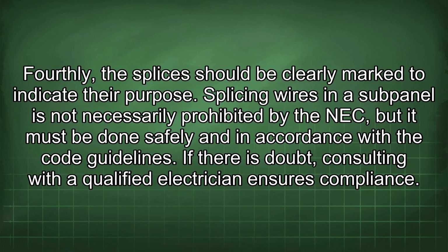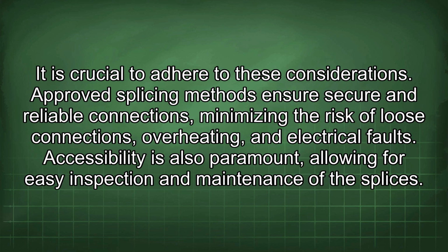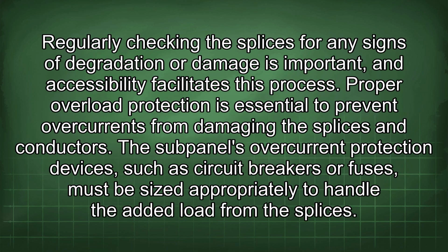Splicing wires in a subpanel is not necessarily prohibited by the NEC, but it must be done safely and in accordance with the code guidelines. If there is doubt, consulting with a qualified electrician ensures compliance. It is crucial to adhere to these considerations. Approved splicing methods ensure secure and reliable connections, minimizing the risk of loose connections, overheating, and electrical faults. Accessibility is also paramount, allowing for easy inspection and maintenance of the splices. Regularly checking the splices for any signs of degradation or damage is important, and accessibility facilitates this process.